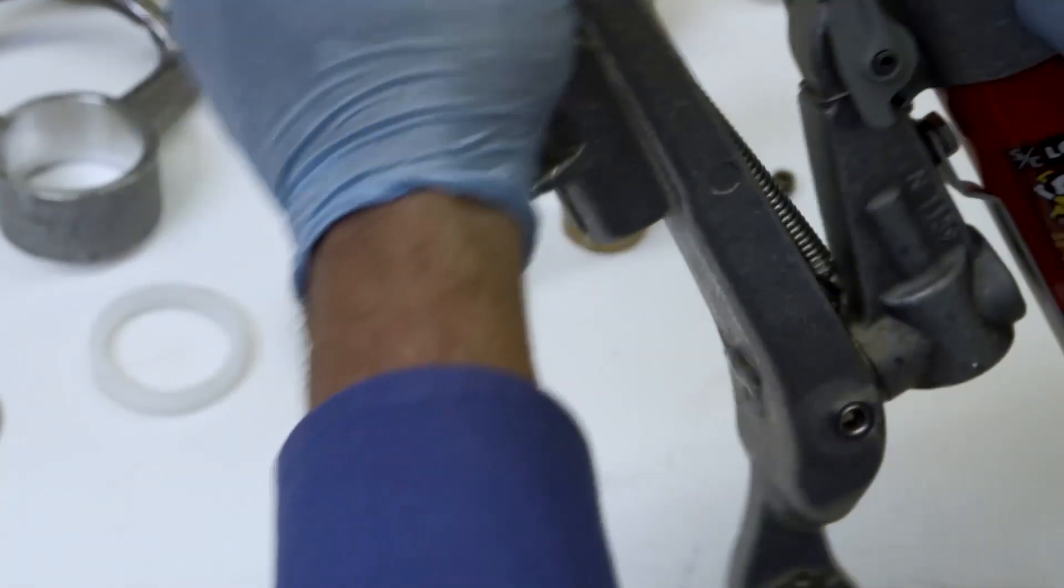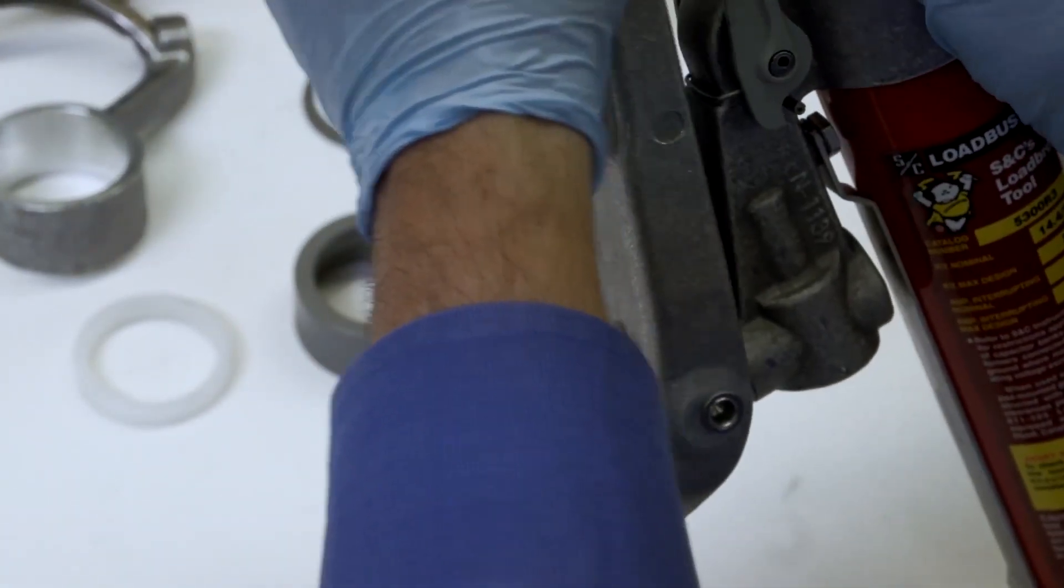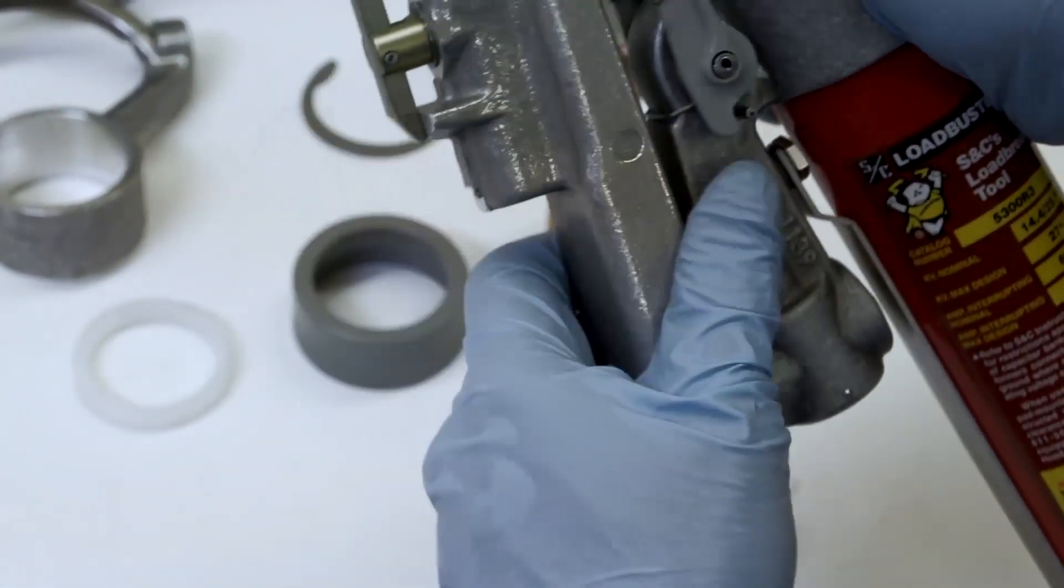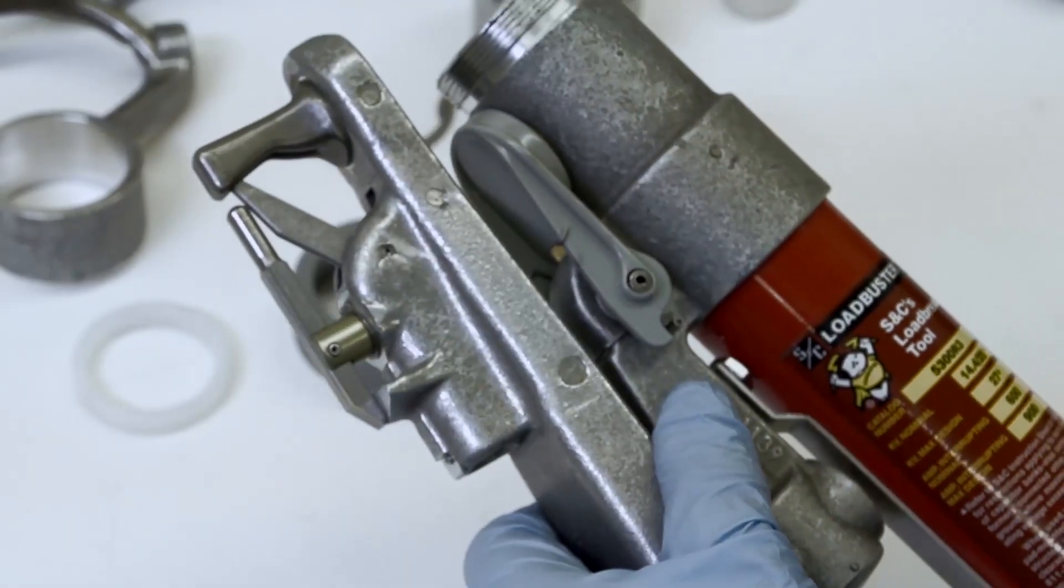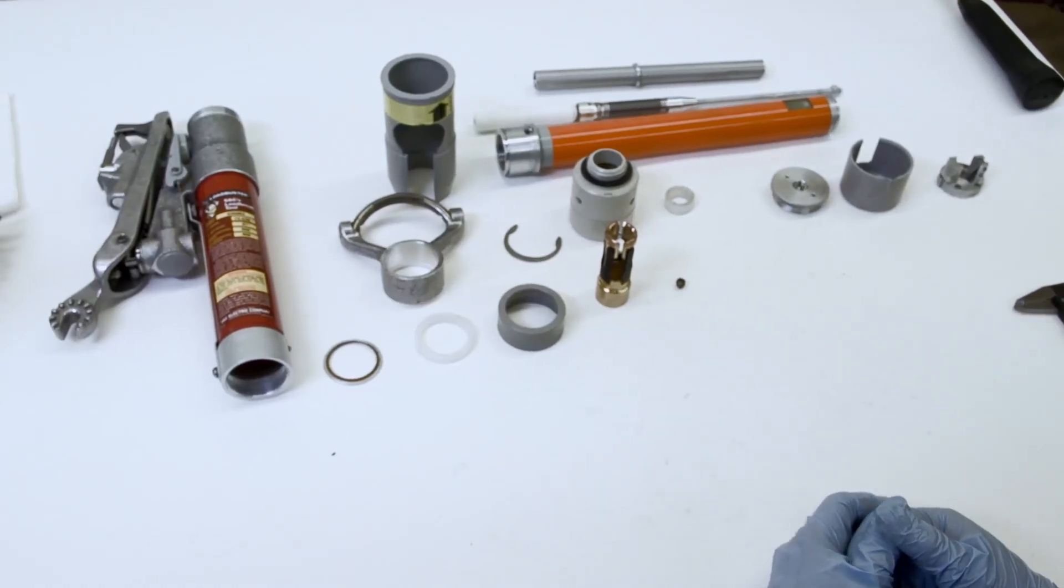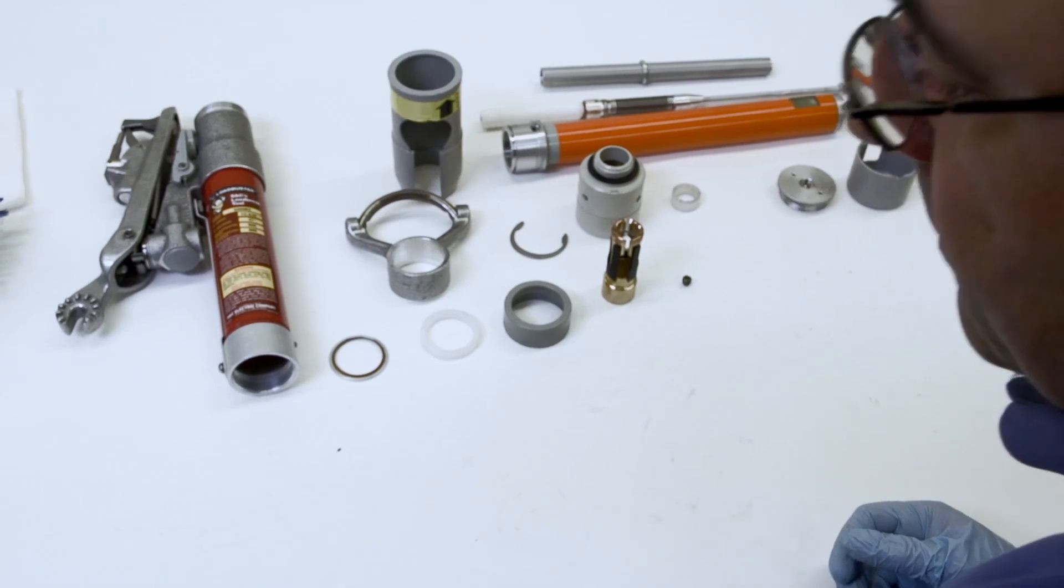This is a critical joint. If the hook frame assembly does not rotate freely, it may be necessary to replace the chassis. Contact your nearest S&C sales office for more information.